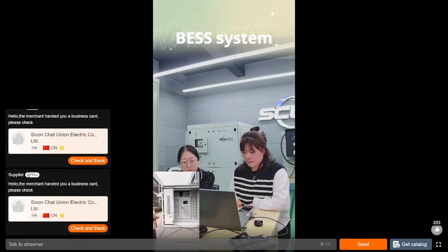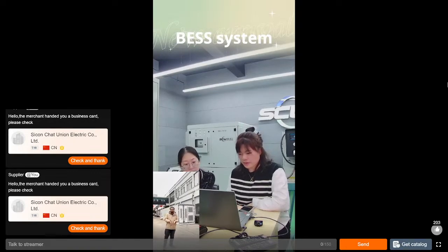And I would like to introduce you more. So alright guys, I'm Totem from Sicon, and I will try my best to introduce you to our other energy storage product. The energy storage product you were seeing behind me is a 40-feet container energy storage, and the energy capacity is 1.8 megawatt per hour. Yeah, that's huge. So I will try my best to explain what's going on and how we designed the system.